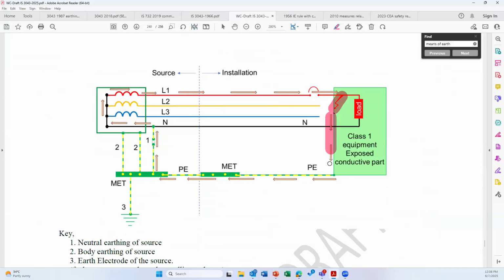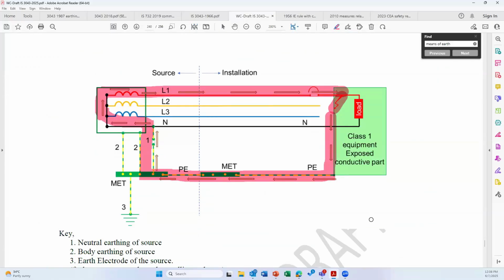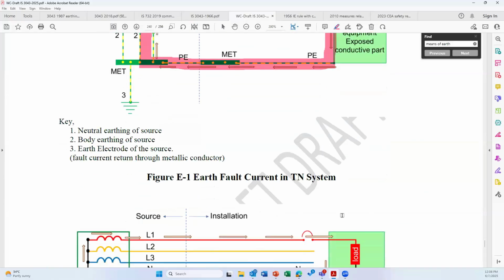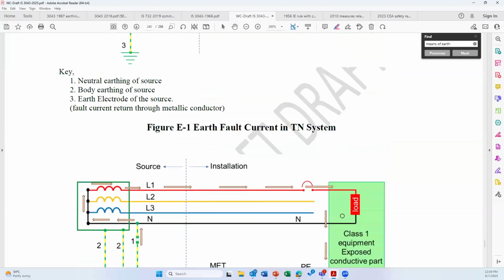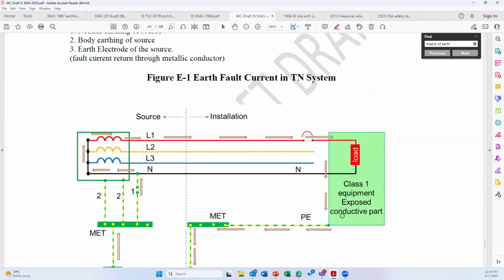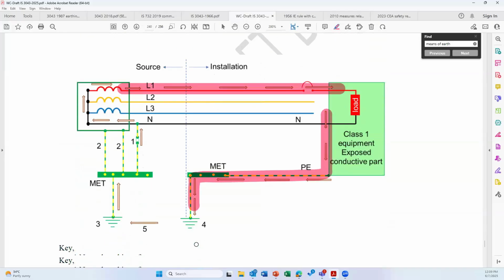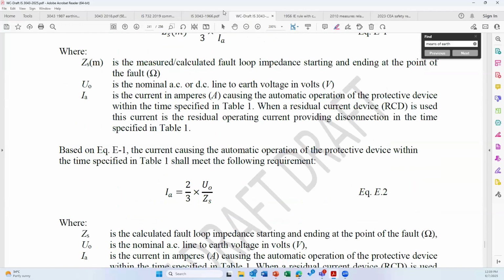So here there is an earth fault. The fault current goes back through the PE, through the metallic fault return path, and in a TN system, this is the earth fault loop, and the impedance of the loop decides the amount of the earth fault current, and the amount of earth fault current decides the tripping time. In case of a TT system, here you can see the fault current goes through the earth electrode, through the general mass of earth, and returns back to the source. So these figures are being included.